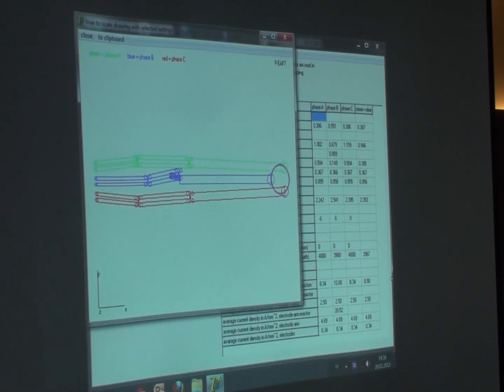The point is, these are 6 lines. You need 6 flexible cables, and you need 4 hydraulic systems - one for this, and 2 for the outside phase, or for the middle phase. We call this the knapsack connection for steel plants. There were some of these constructions in Switzerland, especially.